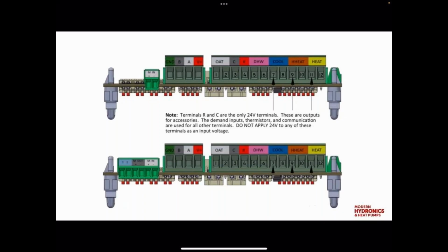Well, definitely integrating that piping into the back of the boiler is a first as far as I know, and it does make for a nice clean install. And the other thing that I believe is a first and maybe unique in the industry is that modulating output. So instead of just turning a ModCon boiler on and off, you're actually able to dial in how much supplemental heat you need from that boiler. So it really works well in concert with the variable speed pump and the variable speed compressor in the heat pump.